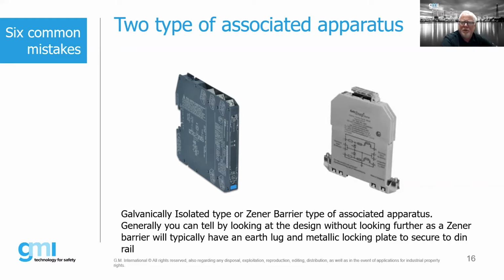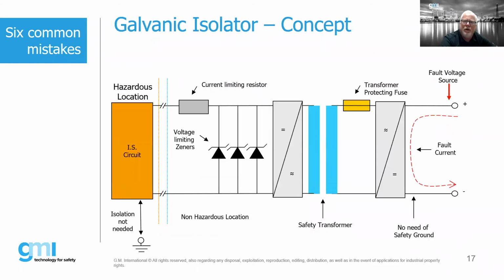An easy way of telling just by looking at a particular product: down on the right-hand side, and I don't know if you can see my mouse, you'll see these little tabs here. Yeah, we can see the mouse, Bob. Okay, thank you. So that's usually a dead giveaway that most likely it's a Zener barrier type, and that's used for providing your IS ground. So the galvanic isolator concept, basically the main difference is that we have in effect a safety transformer located between the potential source and the device in the field. We still have things like current limiting resistors, we still have Zener diodes, but basically we're replicating that signal from the safe area into the hazardous area.